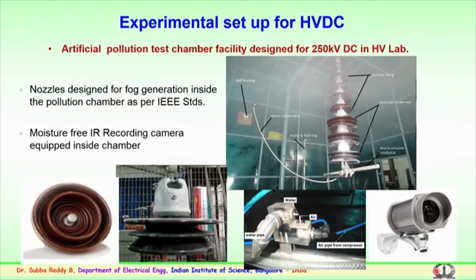So, here in the laboratory we have developed the experimental setup for conducting pollution flashover, pollution withstand or pollution performance experimentation on various types of newly developed insulators by the manufacturers in the country. These insulators are being used for various high voltage HVDC transmission lines in the country. Several new types of insulator discs developed by well known manufacturers in the country are being experimented. The facility which we have developed exclusively for pollution performance for HVDC has a capacity of 250 kilovolts with a 100 milliamps source.